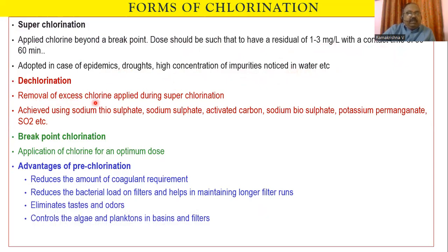Dechlorination. Removal of excess chlorine applied during superchlorination. You're already applying extra chlorination, it should be removed. This is achieved using sodium thiosulfate, sodium sulfate, activated carbon, sodium bisulfate, potassium permanganate, sulfur dioxide, etc. Then we have breakpoint chlorination. This is an experimental determination of optimum dosage of chlorine.